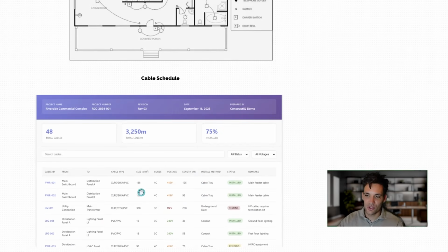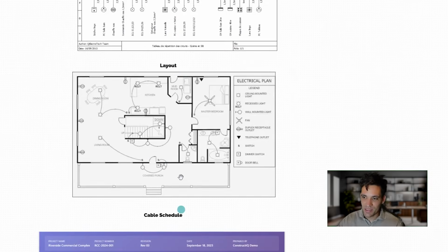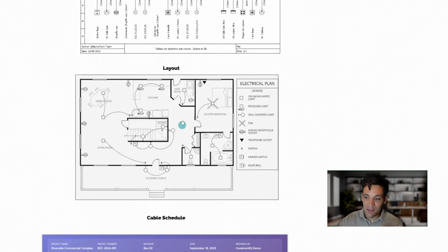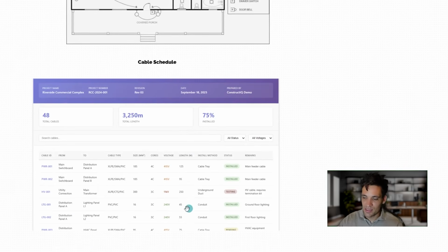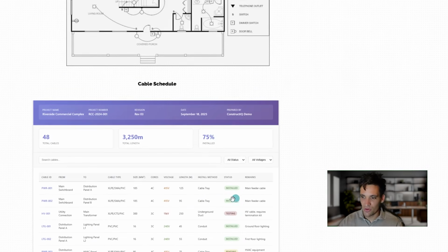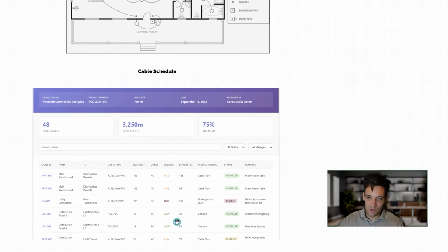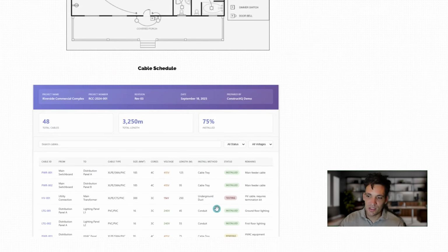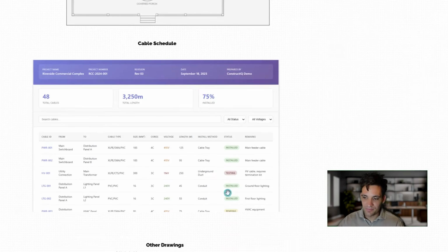What a cable schedule shows you is, for each cable in this system, how long it is, what the size of the cable is, what the expected voltage drop is, how it's installed, and so on. This is a cable schedule. It shows you exactly that from the main switchboard to distribution board A, there's a 185mm cable. It's 4-core. It has these specifications. The cable schedule is going to be your key to both ordering the cables you need and then installing them.